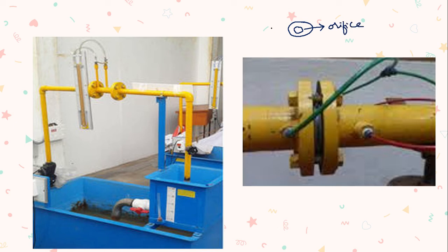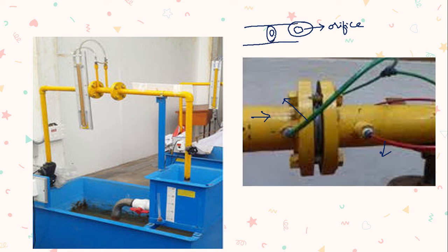Imagine the orifice plate in a vertical orientation — this is how it looks. We fit this orifice meter in between a pipeline to calculate the discharge. The two sections of the orifice meter are connected to the two ends of the manometer to determine the pressure of the fluid flowing through it. One section is connected just before the entrance of the orifice, and the second is connected just after the fluid passes through the inner orifice.